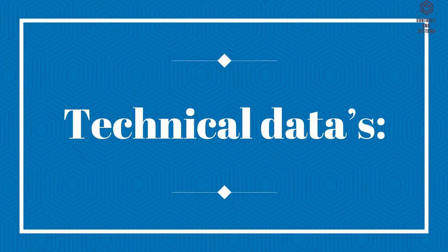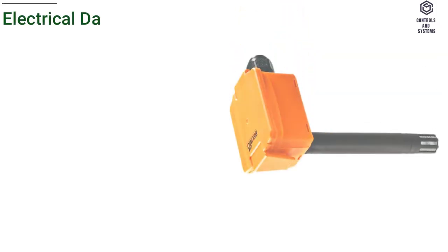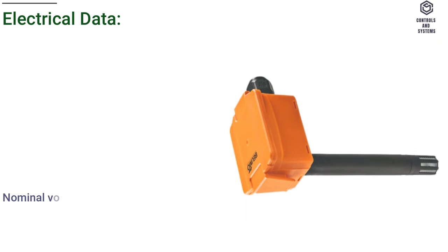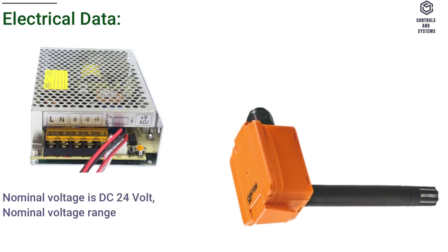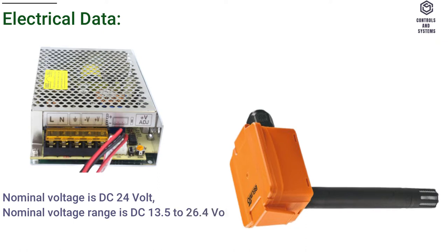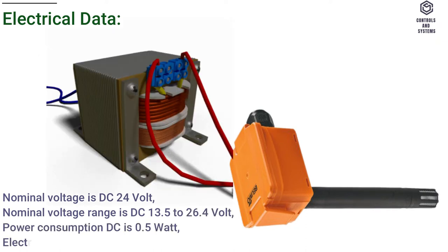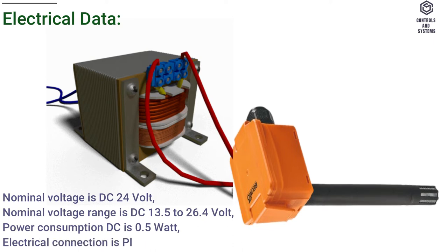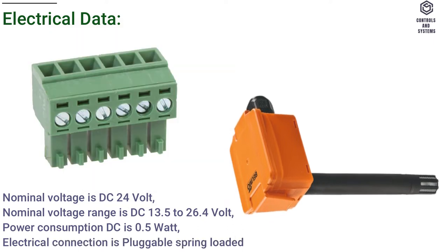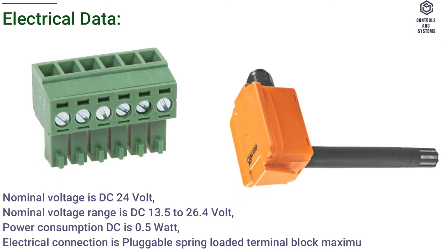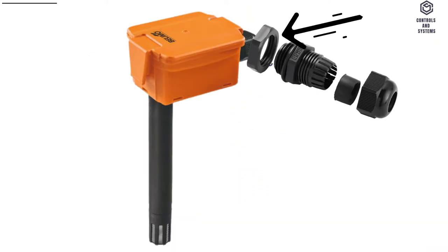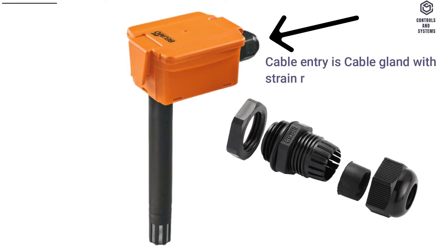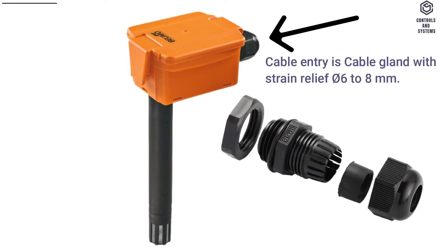Technical Data — Electrical Data: Nominal voltage is DC 24 volt. Nominal voltage range is DC 13.5 to 26.4 volt. Power consumption DC is 0.5 watt. Electrical connection is pluggable spring-loaded terminal block, maximum 2.5 mm². Cable entry is cable gland with strain relief, ∅6 to 8 millimeters.